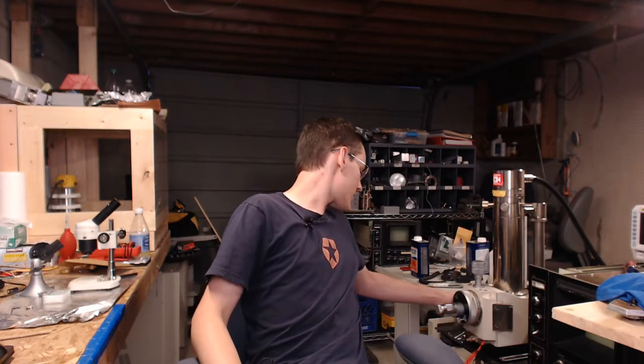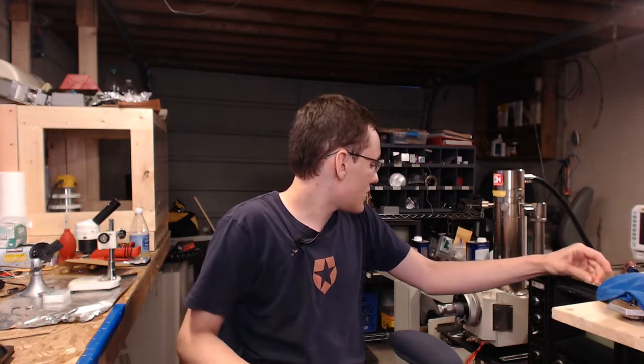Yeah, it still feels like it's got a pretty good vacuum in it. So go ahead and get that thing pulled back to vacuum again, because I want to give it a little bit longer to outgas at a really high vacuum. In the meantime, we'll get the scintillator rebuilt, and by then the SEM will be done outgassing and we'll be ready to start it back up and hopefully zoom in a lot further. I've just barely hit 10,000 times magnification, and I should have no problem getting to 100,000 times magnification. So I've got an entire order of magnitude left to get out of this thing.